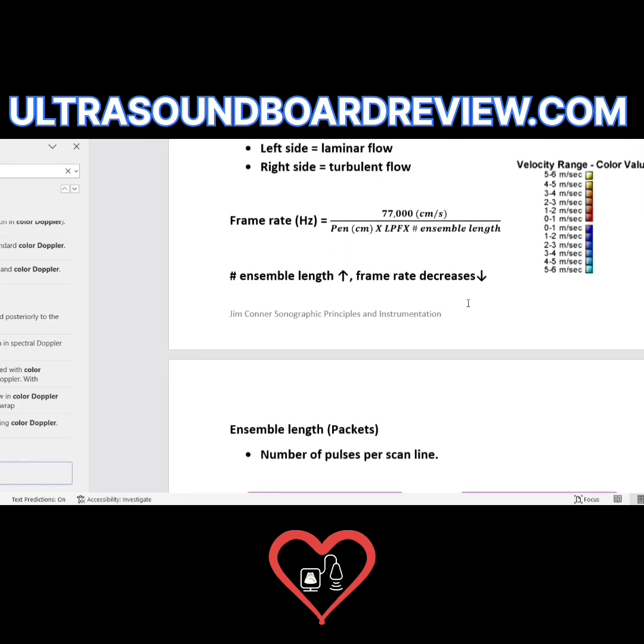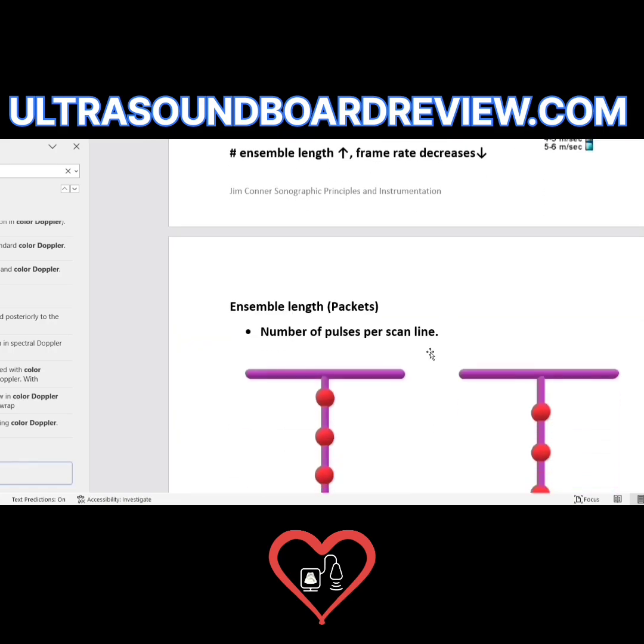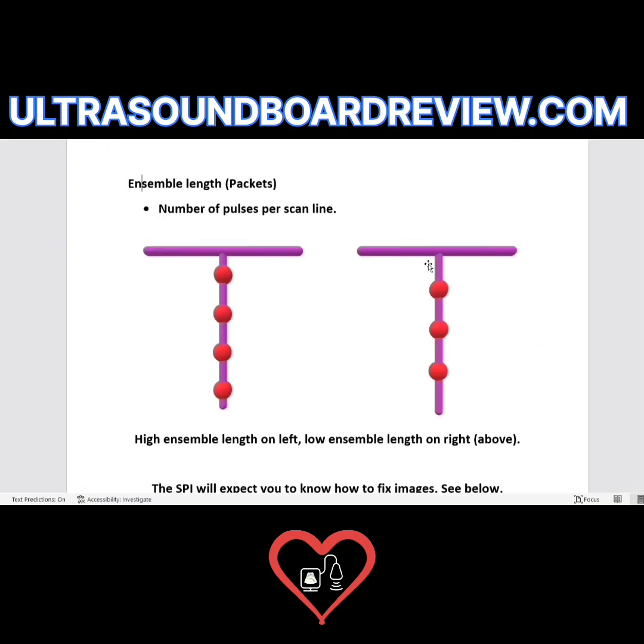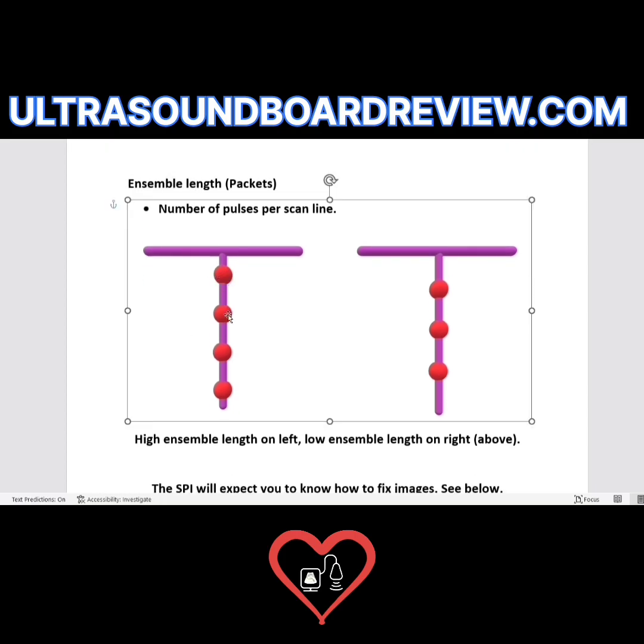The reason we get color Doppler in the first place is the ensemble length, which is the same thing as packets — the number of pulses per scan line.